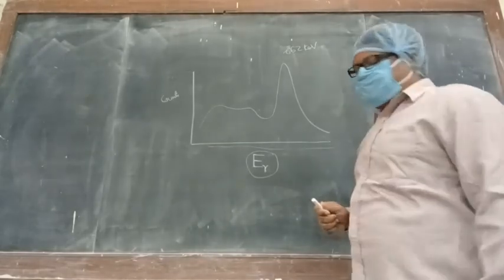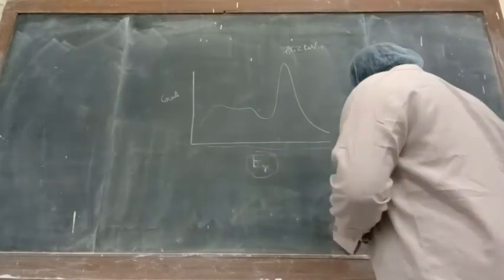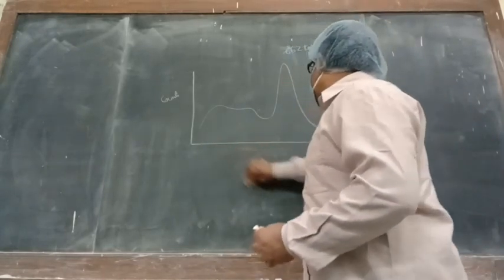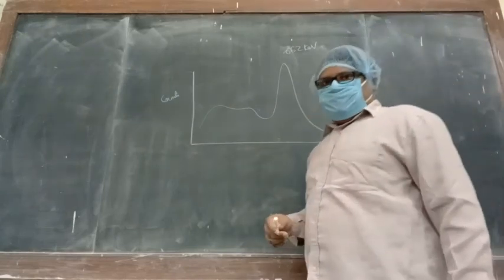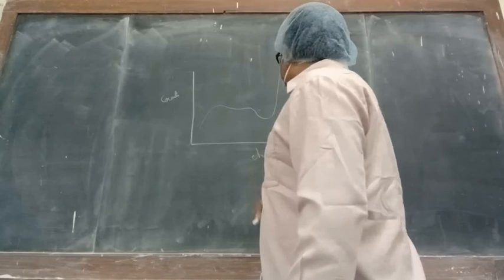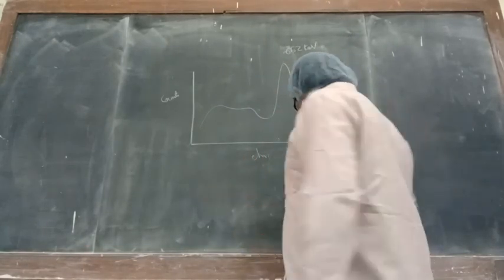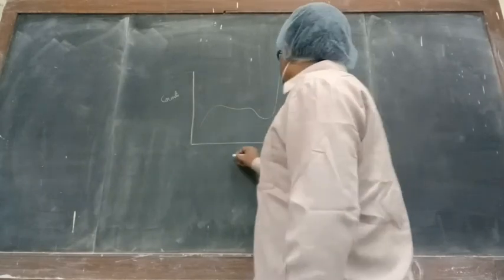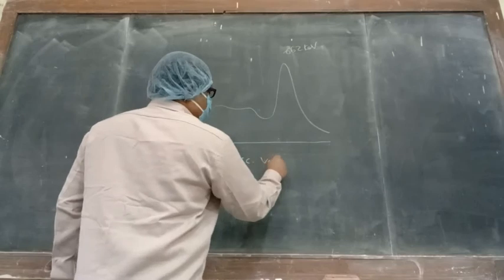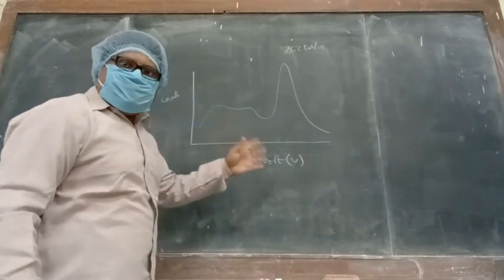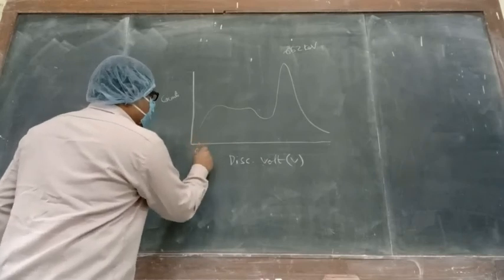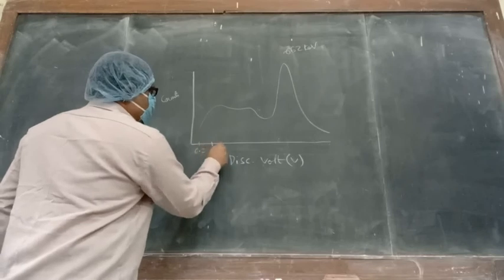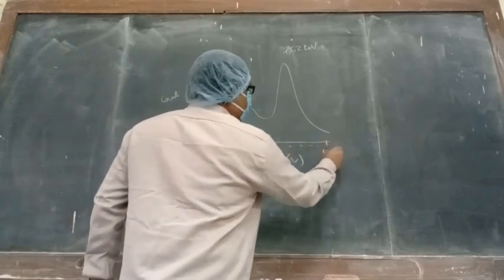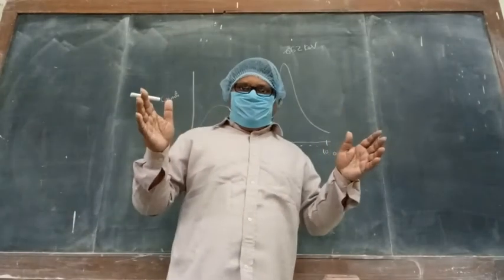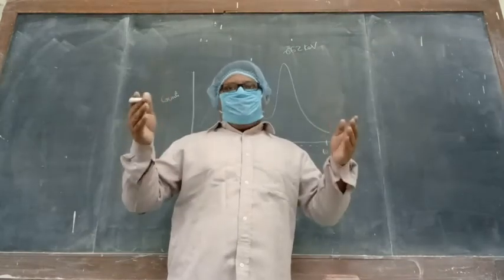this we will not get because we do not know it. First we have to calibrate this axis, and how do we do that? Instead of E gamma, we do this plot in terms of channel, or discriminator voltage. So as I have shown you just now, we will be doing this plot in steps of 0.2. So from 0.2, 0.4, and so on and so forth, up to 10, because this is the maximum limit. We can take the data in this entire range of 0 to 10 volts.